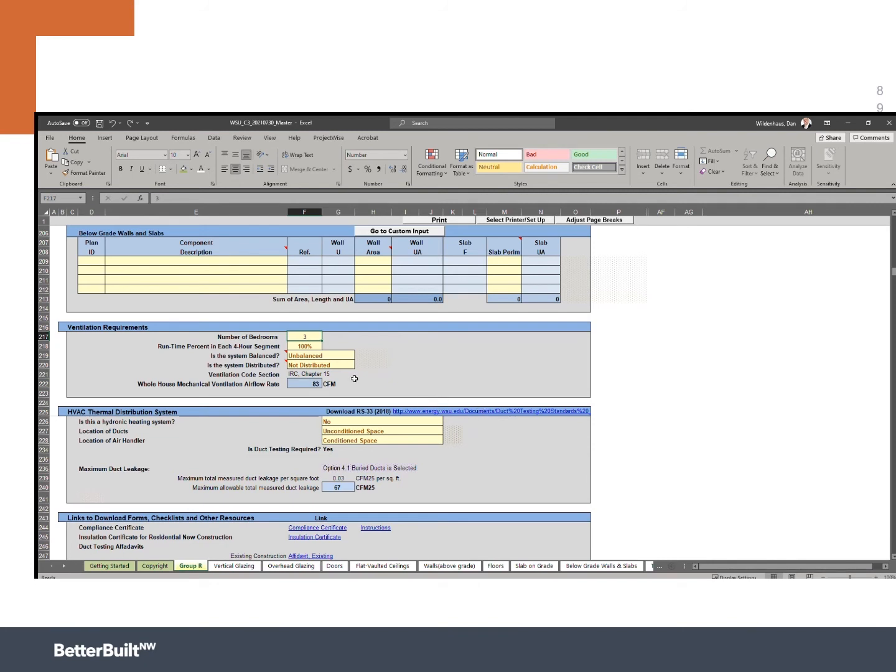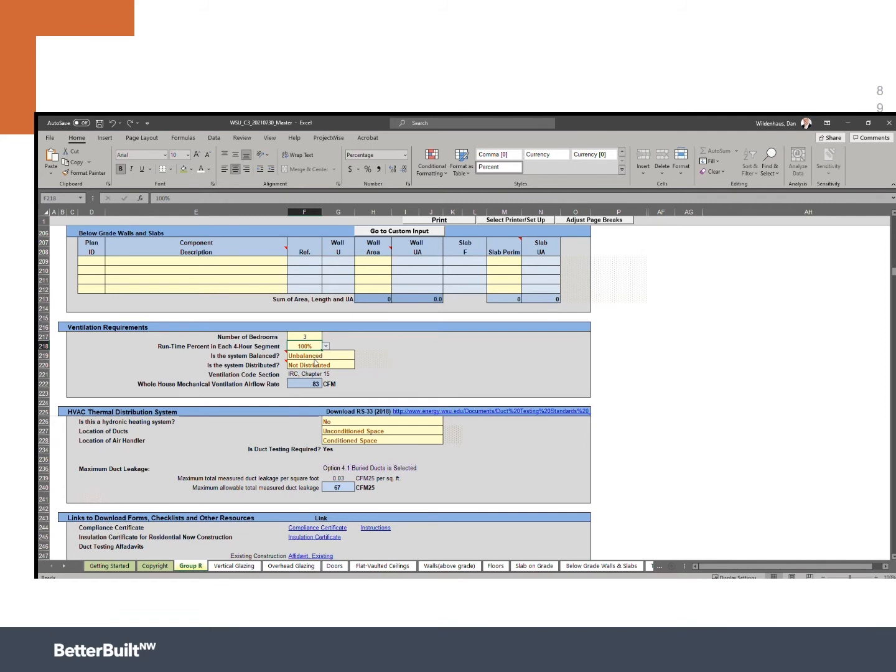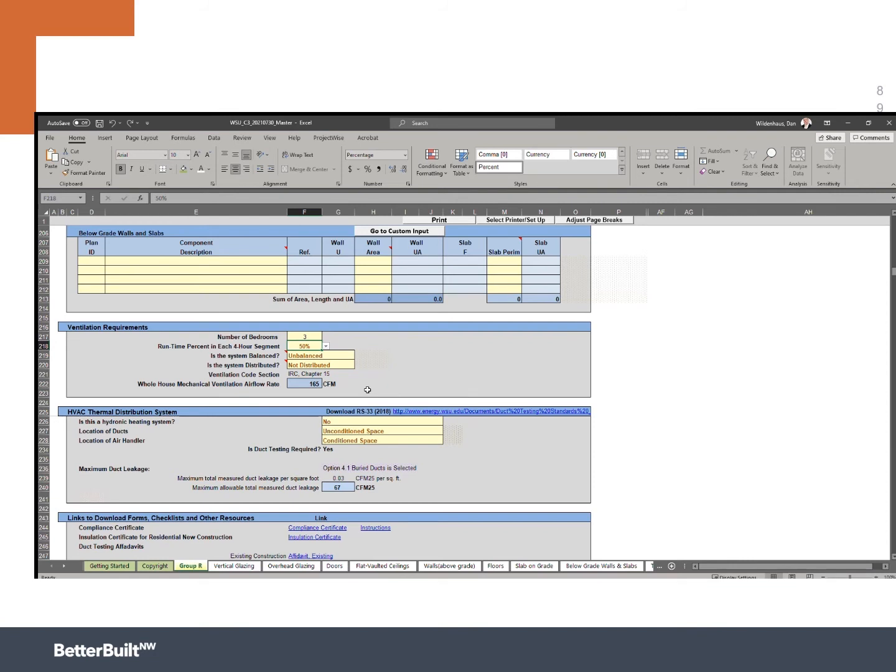But what if I didn't want to run it all the time? What if I wanted to run it half the time? This becomes a little pull down where it says 100% and I can switch it to 50%. Now take a look at that. We're now being required to do 165 CFM. Now there's not a lot of really great single exhaust fans that are also Energy Star qualified and are low enough sone rating, which is quiet enough, that 165 is going to be a good idea. So you could do that with two exhaust fans running at each at 50% of their time. That could get you there.